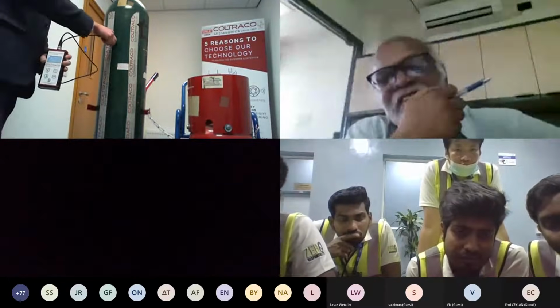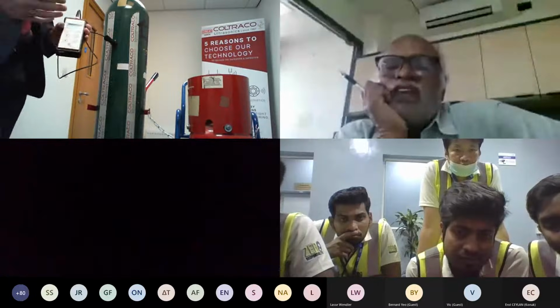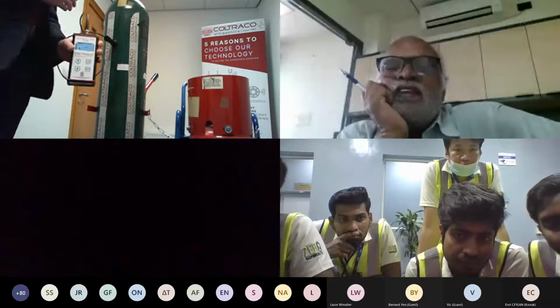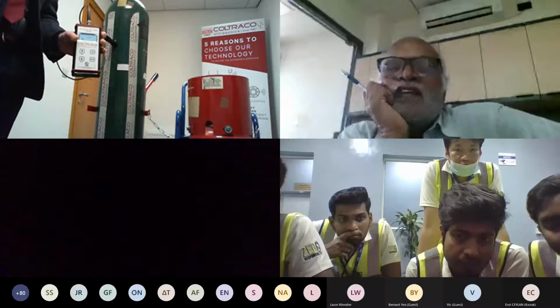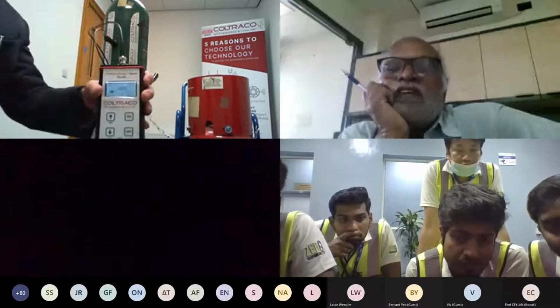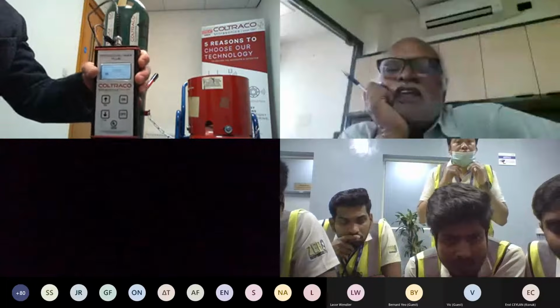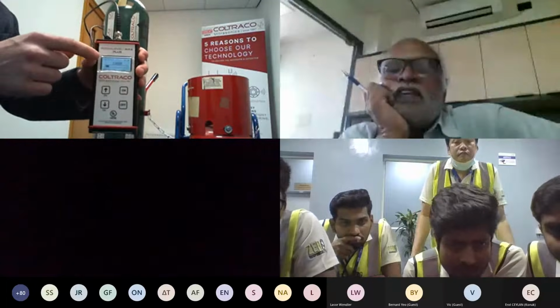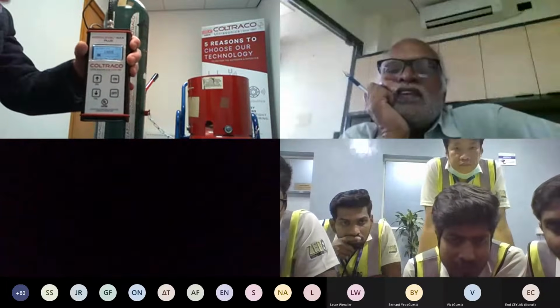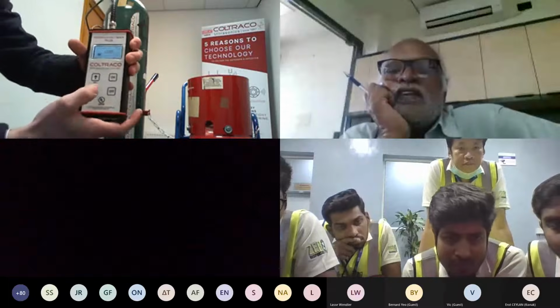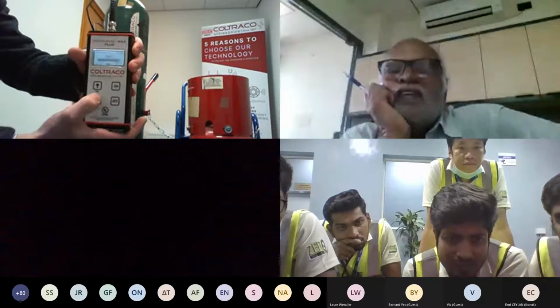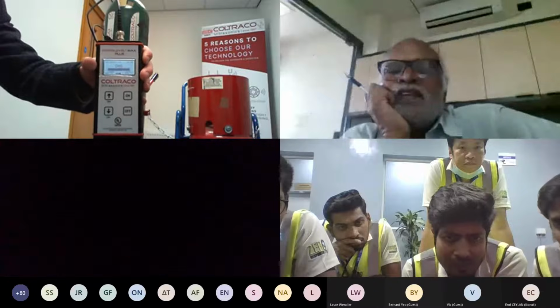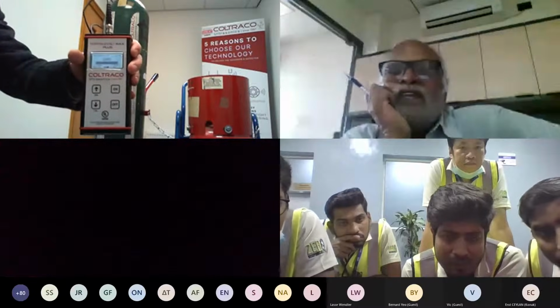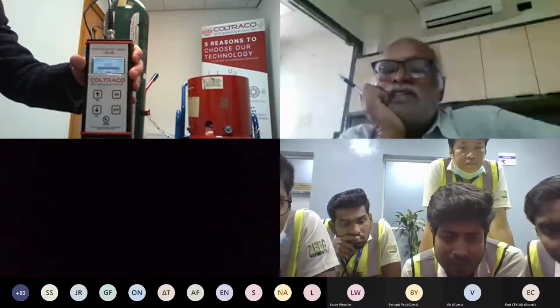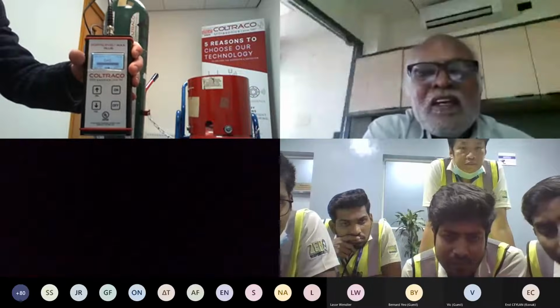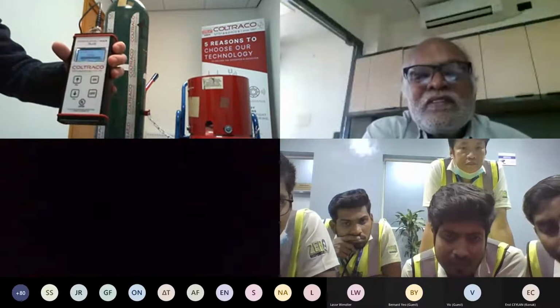So I move the sensor back up into the high reading area. In this case, because the difference in the readings is quite large, what I do is I calibrate around the average high reading. So, as you can see, this isn't the highest reading that I received on the cylinder. I'm calibrating around the average high. So what happens now when I press the cal button? As you can see, the display changes and it now reads gas. Gas is the default because on most cylinders, the highest readings will occur in the gas phase. So that's why it reads gas there.